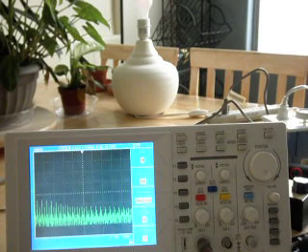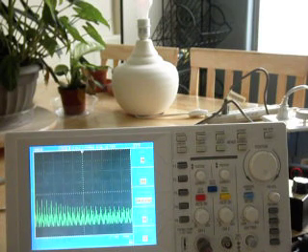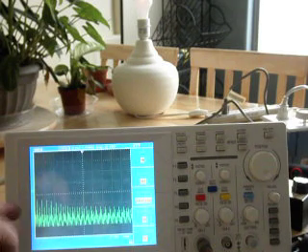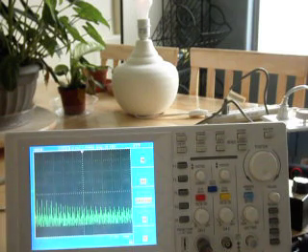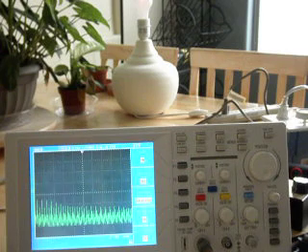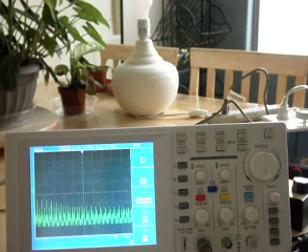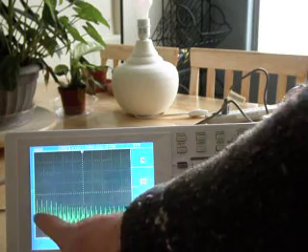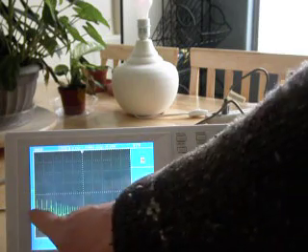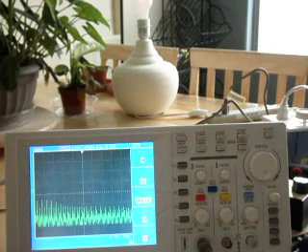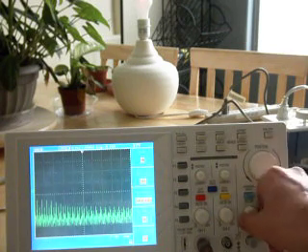The scale that we're on right now is 250 Hz per division. You can see the fundamental harmonic on the left, which is 60 Hz, and the rest are the odd harmonics coming off the lamp dimmer. The smaller spikes in between are actually the even harmonics. So we've got quite a mix of harmonics in there, and those harmonics keep on repeating almost indefinitely.